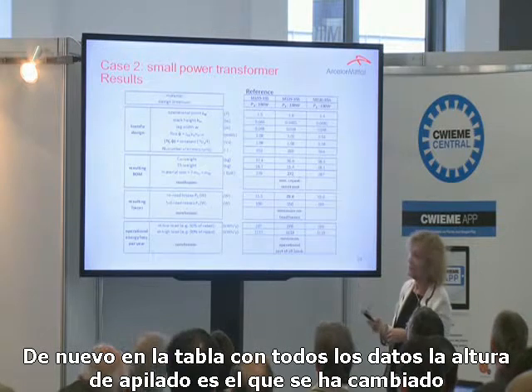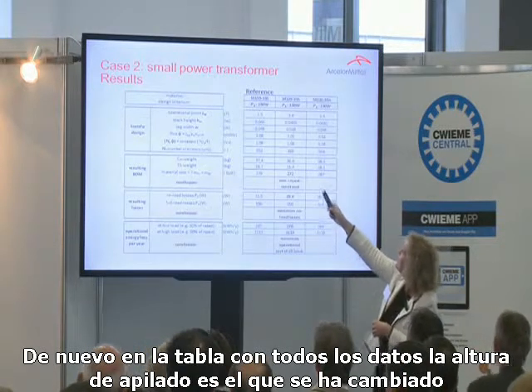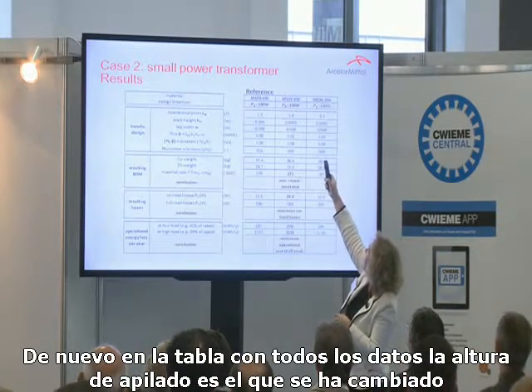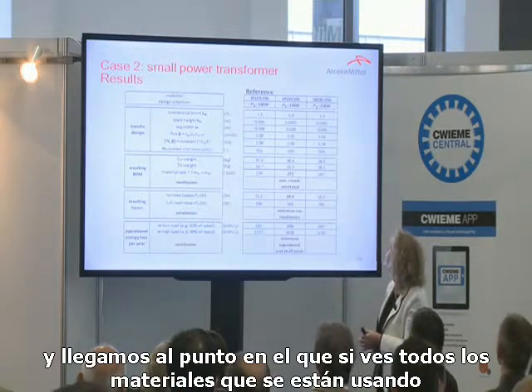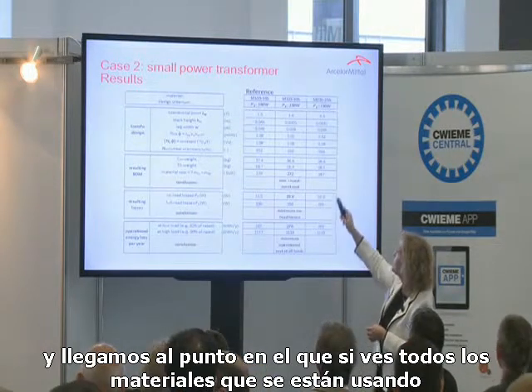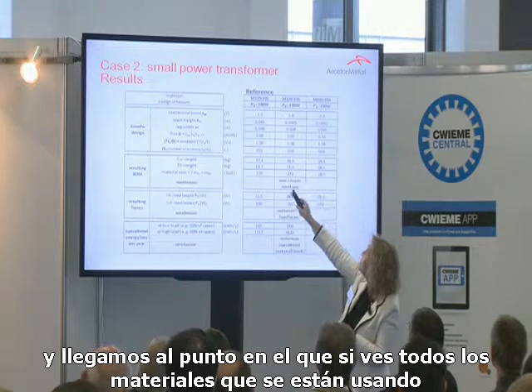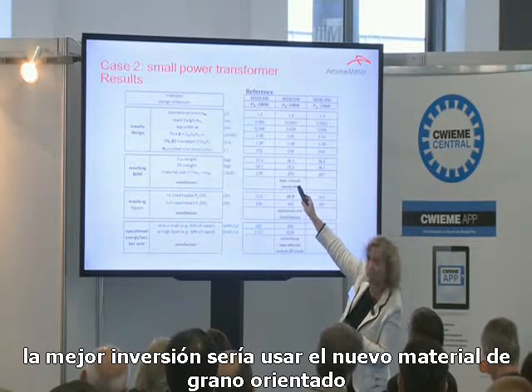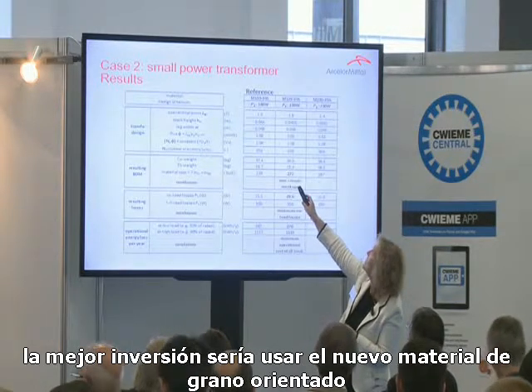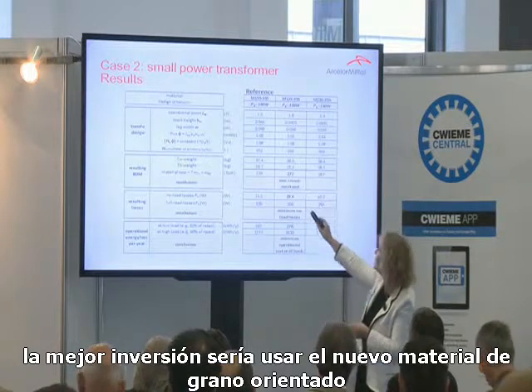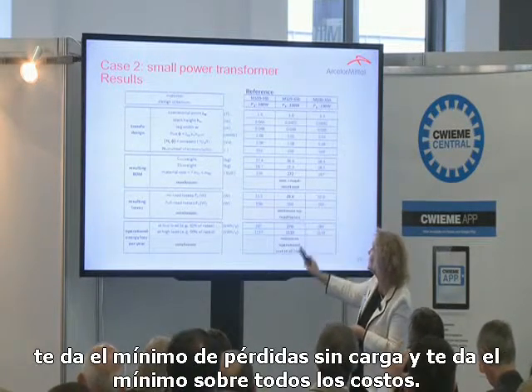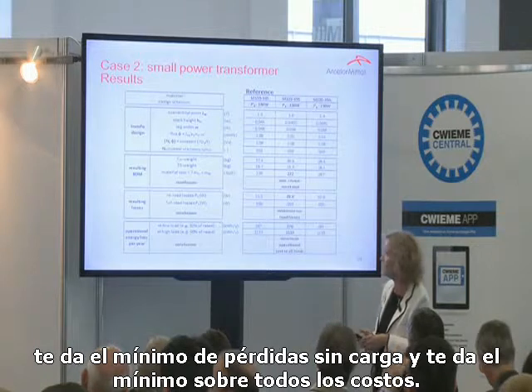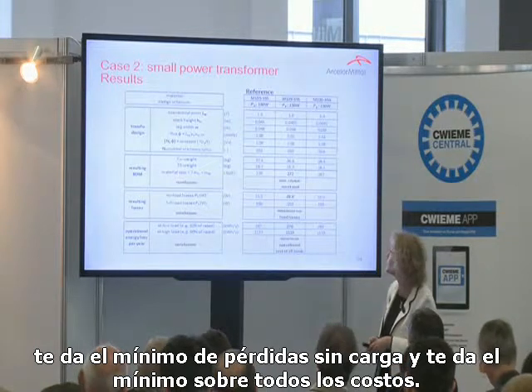Again, a table with all the data. The stack height is the one that has been varied, and we come to the point that if you look at the total amount of material used, the best investment would be to go for the new grain-oriented material. It gives you the minimum no-load losses and the minimum overall exploitation costs.